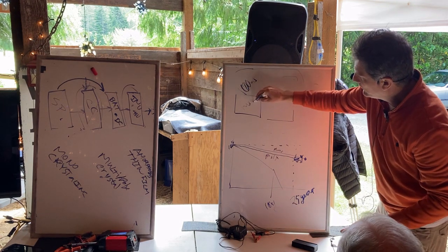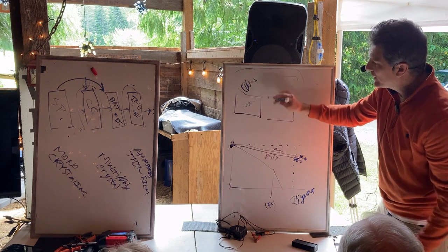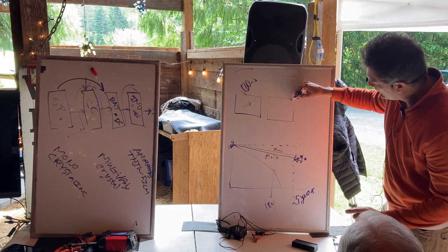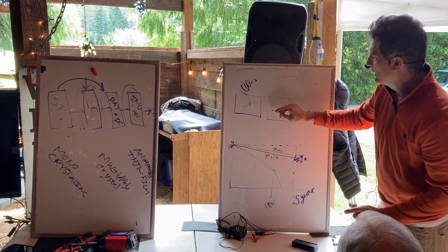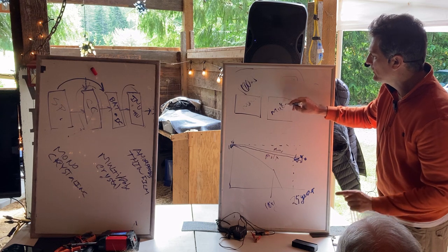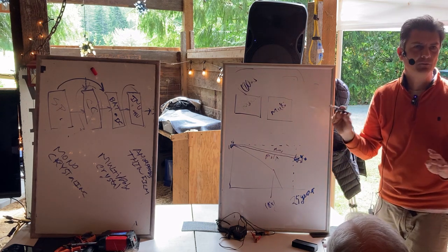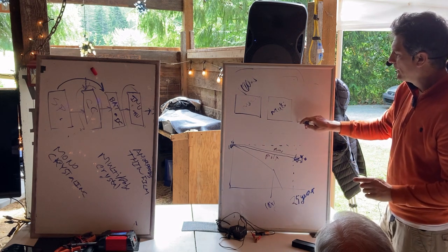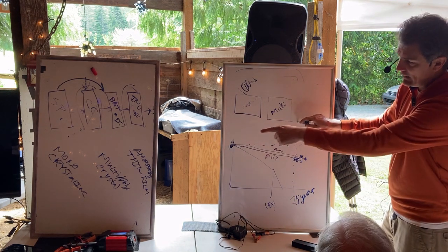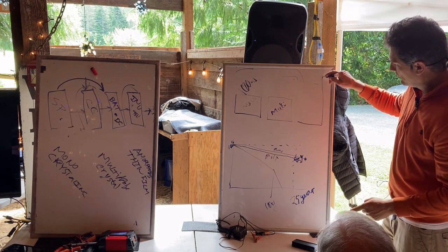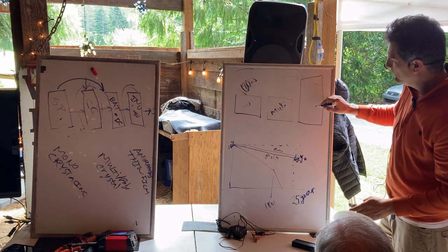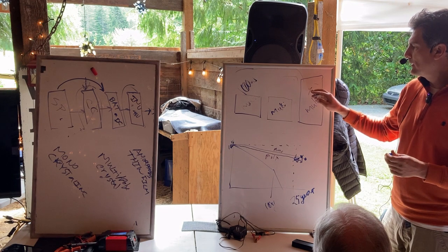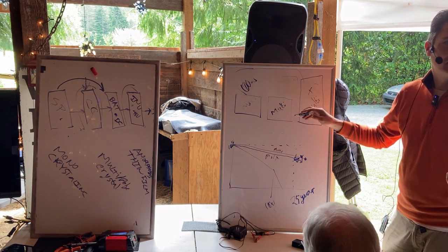Okay, 100 watts. The panel's going to be that. Multicrystalline, generally, it's going to be a little bit bigger. This is multi. What it means is it's not as efficient. So when you look at the efficiency numbers on these things, that's where these become different. And then if you use an amorphous, it's going to take this big. All for the same power. I avoid these almost all the time, just because you're going to get 10 years out of the thing.